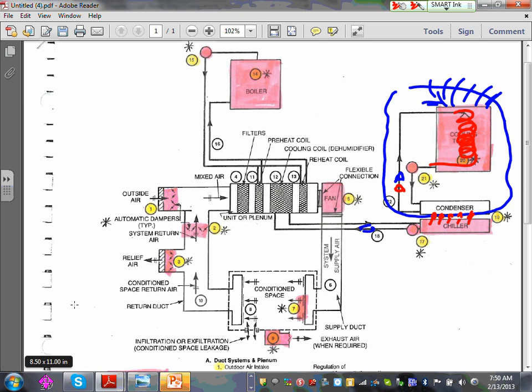A coil is a pipe, looped, and they put big fans on the bottom, throwing air right through it. Sometimes they have water actually dripping on it, too. They're cooling that water inside the pipe to bring it back here, to pick up more heat, take it back again, throw it up in the air, come back, pick up more heat from the building, and that's how they chill the building, by removing heat from the building. Any comments, guys? Any questions? So here's your cooling tower, coil with condenser, and of course, what moves the water? Pumps. You have tons of recirculating pumps that take the water all the way to the cooling tower and bring it back again to the condenser to chill it, or to pick up more heat, take it back, throw the heat out, and you keep repeating the cycle of removing heat.